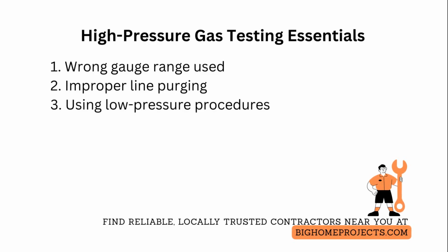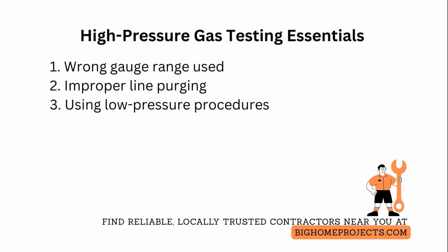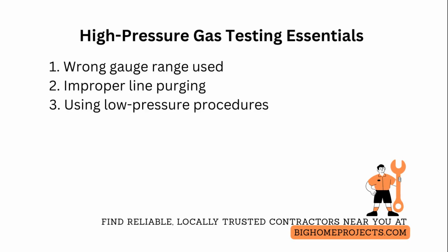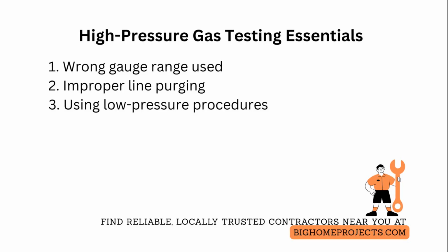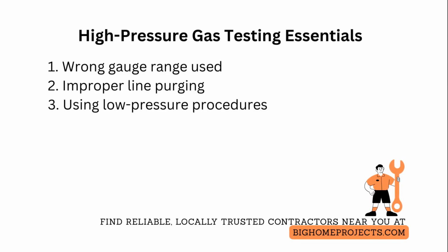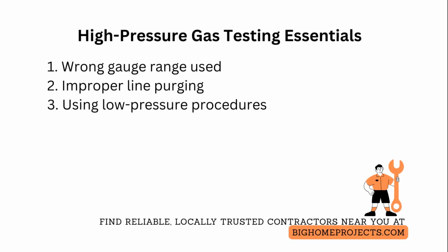once purged. The third typical error is applying generic low-pressure test procedures to high-pressure systems, ignoring code-specific test pressures and hold times. Remedy that by consulting the applicable code sections, manufacturer installation manuals, and by calculating test pressures as a percentage above maximum operating pressure with documented verification.